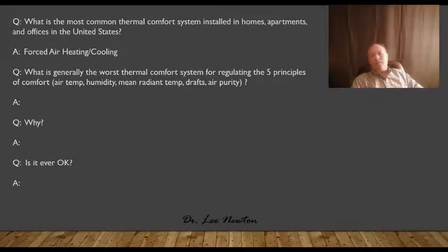Now, I also referenced in a previous video that, yeah, when you're cooling, it's removing humidity from the air. That is correct. So you're controlling air temperature, you're influencing humidity content, but you're not controlling humidity. You don't have a humidistat. You don't say, keep cooling until the air temperature is 70 and the indoor relative humidity reaches 45%. The systems like that may exist, but they're not practical. They're not used. They're not installed in homes and apartments and office buildings.